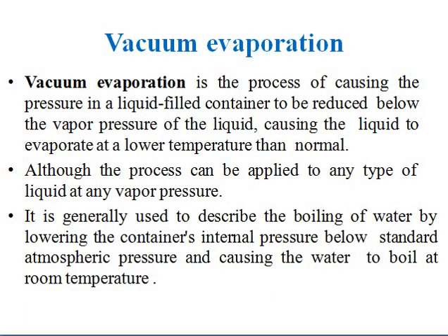Next we are moving to vacuum evaporation. Ultimately all these evaporators are connected with a vacuum, so basically we require lower energy under the vacuum process. Vacuum evaporation is the process of causing the pressure in a liquid-filled container to be reduced below the vapor pressure of the liquid, causing the liquid to evaporate at a lower temperature than normal.